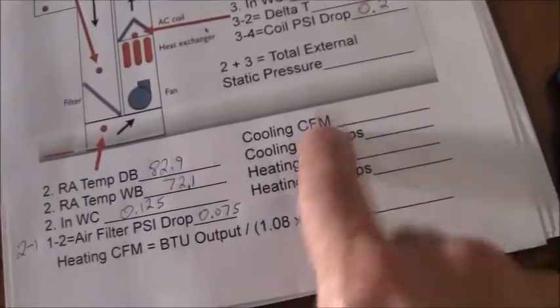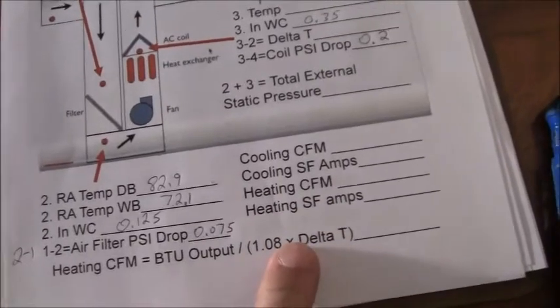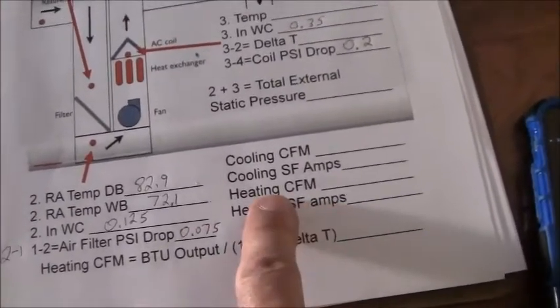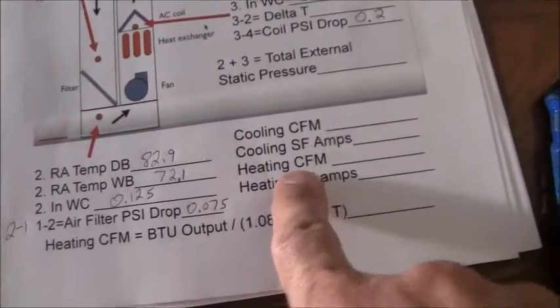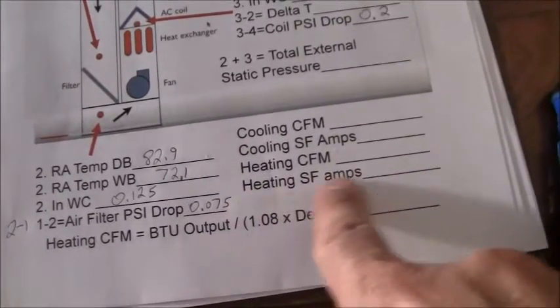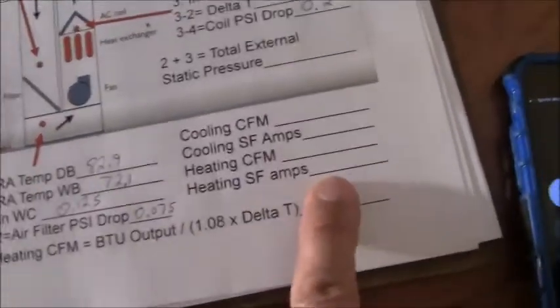Now, we want to know what the amps are. Right now we're in heating mode, so let's go with supply fan amps. Let's figure out what that is right there. My meter shut off, but let's put it back on. Go to amperage AC. There's my backlight right there. And right now the fan is drawing 3.83 amps. Okay, it's 3.83. So let's write that down.